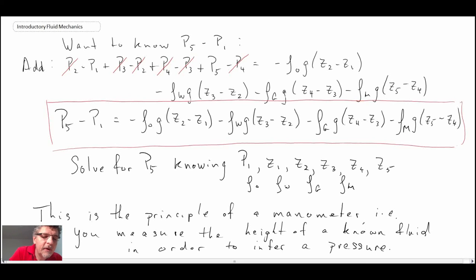This is the principle behind which a manometer works. The principle of a manometer, it's pretty simple. What you do is you measure the height of a column of fluid. That means you need to know the density of the fluid and you need to know where the interfaces are. By doing that, you can then infer a pressure that you are trying to measure.